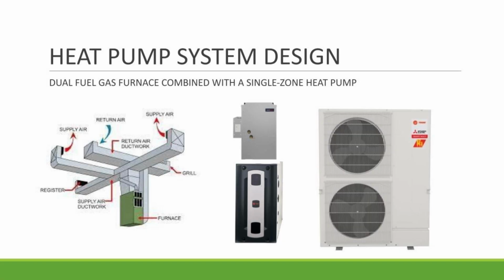Another option could be what's called a dual fuel system. In this case, what we would do is we may have a gas furnace, a propane furnace, or some form of a high efficiency condensing furnace that would serve as a backup to the heat pump system. We could install a cold climate heat pump with an indoor coil that mounts to the top of your furnace. There would be a control via your thermostat that would control the system. It would decide when to switch from a heat pump over to a gas furnace. And the furnace would really just be used as a backup in this type of system.